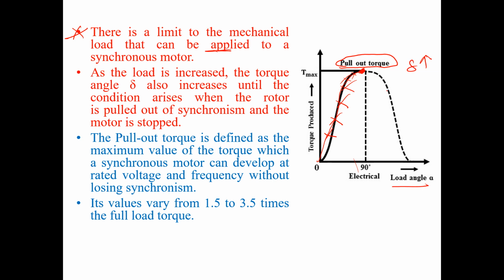But as soon as you go above this, the dotted point, it is the saturated region, that means motor will be desynchronized from the supply system. As the load increases, the torque angle also increases until a condition arises when the rotor is pulled out of synchronism and the motor is stopped, and that will be this position. The value of torque corresponding to this point is known as pull out torque.